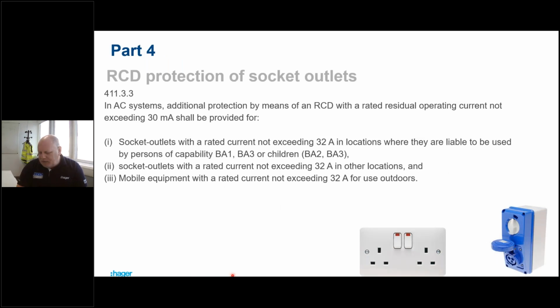So we're going to jump into the regs now, and the first part we're going to jump into is part 4, RCD protection of socket outlets. So the regulation now says that in AC systems, additional protection by means of an RCD with a rated residual operating current not exceeding 30 milliamps shall be provided for. And it gives us 3 areas. Okay, so socket outlets, okay, where they are liable to be used by persons of capability. And it gives us these numbers and letters, BA1, BA3. BA1 is an ordinary person, okay? BA3 is a disabled person. BA2 is a child. So we've got these categories of people. If they're going to use a socket outlet, it must be protected by an RCD.